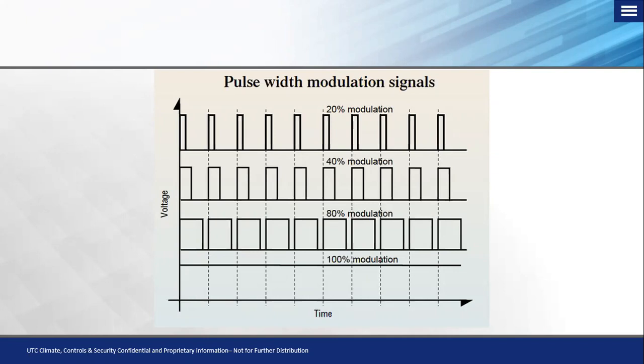If we look at that pulsing as a square waveform, and essentially that's what we need to look at it as, it depends on what incremental pulse we're going to get out of those switches that we just covered, the IGBTs. As you can see here, this isn't the only amount of pulse that is limited to that IGBT. It can pulse anywhere between, but as a representation, we can look at a square waveform as a 20% pulse, 40% pulse, and 80% pulse. Now, what happens here is you have a pulse on the positive side and you have a pulse on the negative side. We get a pulse on the positive, we come down and get a pulse on the negative, and we start simulating the AC sine wave. And this is where that simulation of that pulse width modulation occurs.